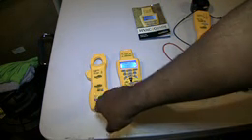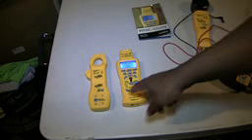And one thing I've learned, which I will demonstrate in another video, is that when you have your blower door open and you're measuring the amperage on your blower motor, your amps will go up. And when you close your blower door, your amps drop back down. At first that threw me off, because it seemed kind of backwards. But then I realized that any type of restriction in your system, whether it be the blower door closing and you build up static pressure, or buildup on your return filter, will cause the amps on your motor to go down.